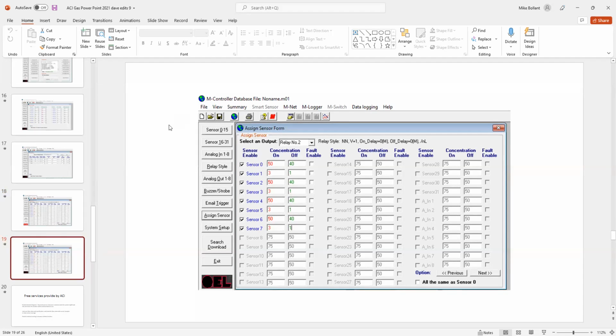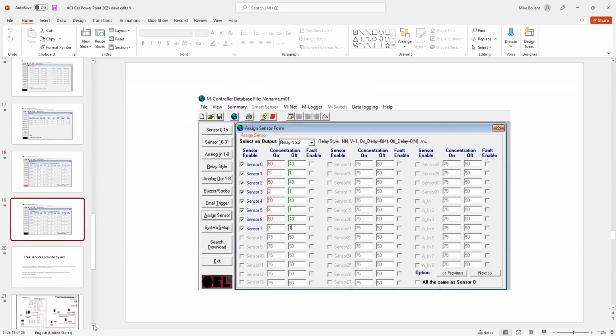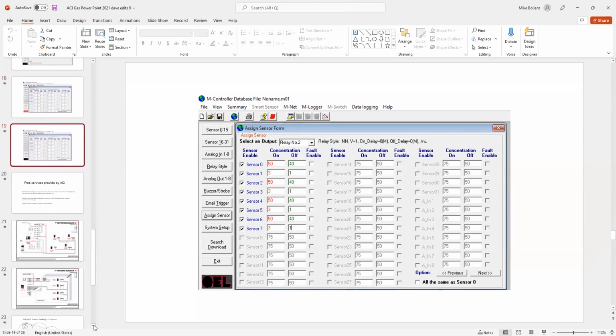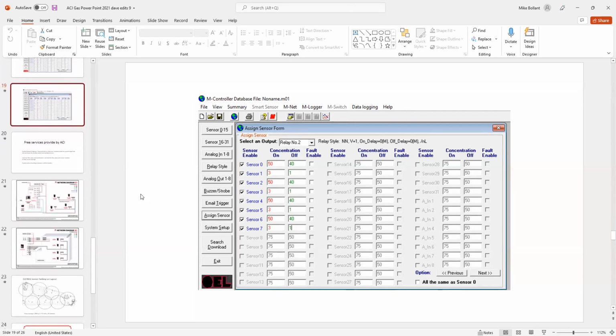And we do the same thing for relay 2. Higher trip levels, 50 and 40, and then 3 and 1. And that will turn relay 2 on. So, then relay 2, your high alarm, that could either be another fan, that could be a horn and strobe back at the superintendent's office, or even, set up another relay 3, that could be a dry contact to the fire alarm panel.